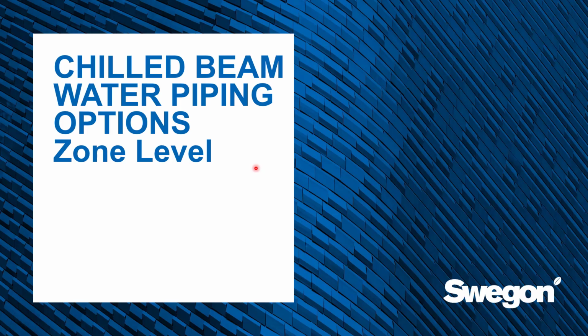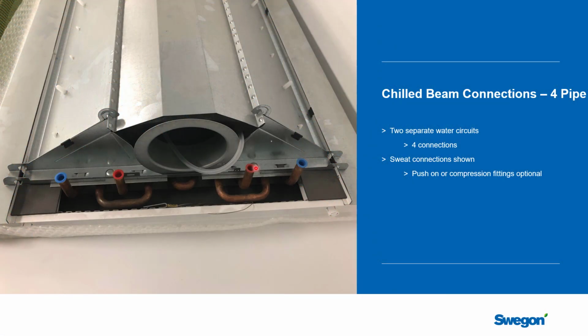In this video, we're going to consider chill beam water piping options at the zone level. To get started, the first thing we want to remember is that chill beams, just like fan coils, come in either 2-pipe or 4-pipe. So here's a picture of a 4-pipe chill beam. You can see the blue connections are marking out the chilled water loop, and the red connections are marking the hot water loop. So this coil slab has 2 separate water circuits in here.